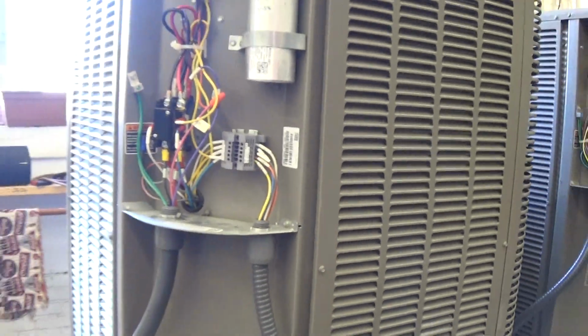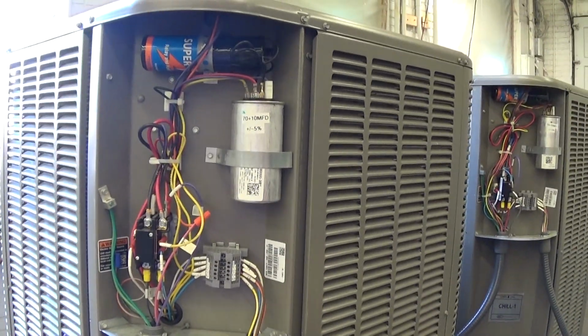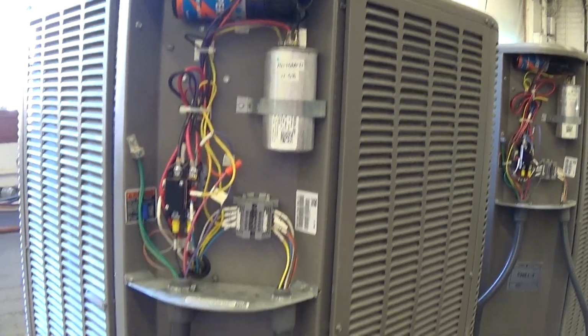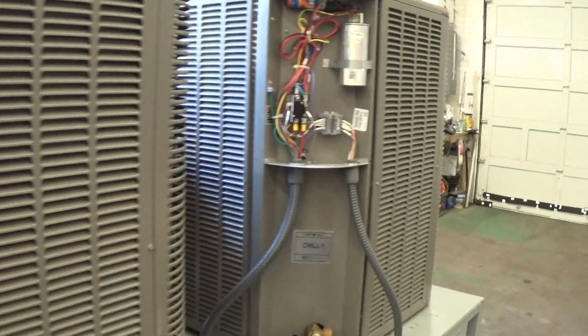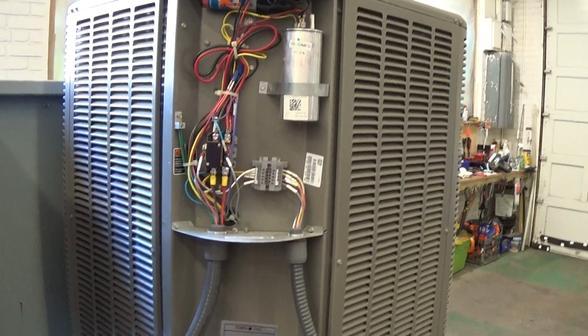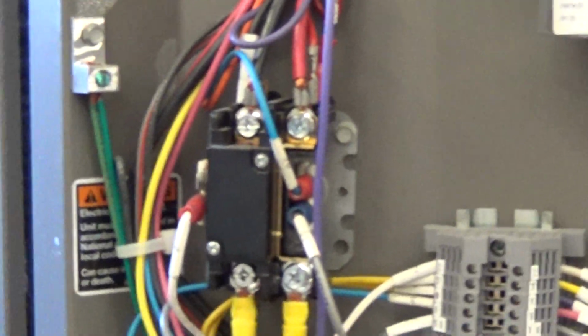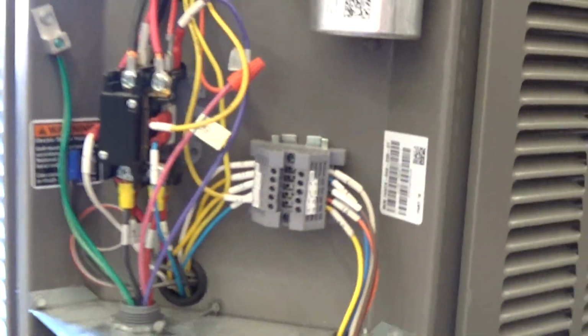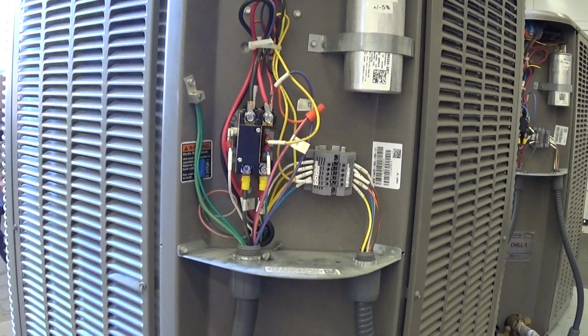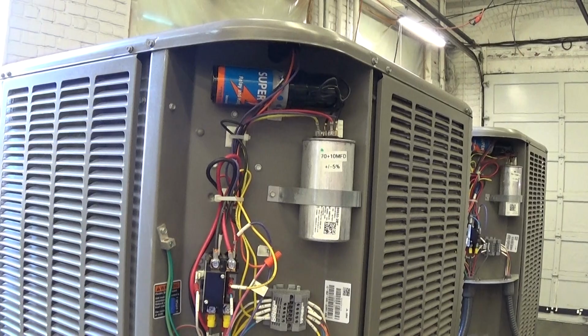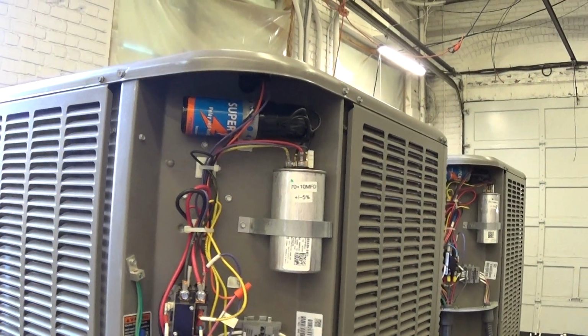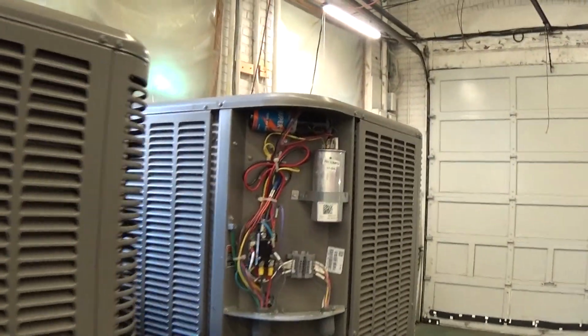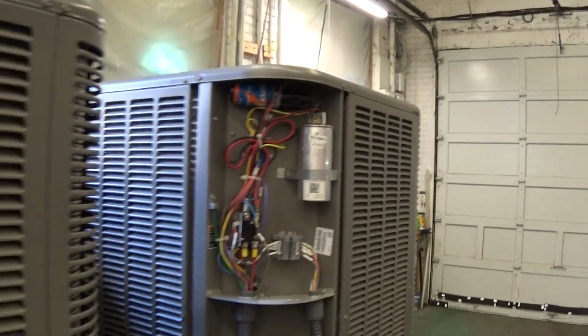Just for our own operation and testing here, we have the covers off of each condenser up top here. That's where the compressor contactors are. We just have those off to check the condition of the contactors. And also while we were testing, we like to put an amp meter on there and see what they're drawing. And that's the hard run capacitor for each compressor and the capacitor for the fan.